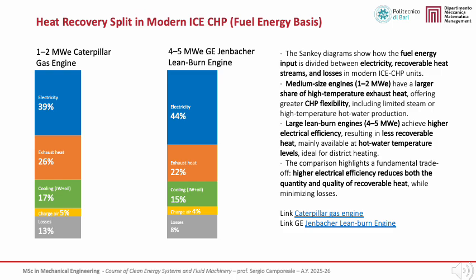This comparison highlights a fundamental trade-off in ICE-based CHP systems. As electrical efficiency increases, both the quantity and the quality of recoverable heat tend to decrease, while overall losses are minimized. For this reason, medium-size engines offer greater flexibility, including limited steam or high-temperature hot water production, whereas large, highly efficient engines are particularly well suited for district heating applications, where heat is mainly required at hot water temperature levels.